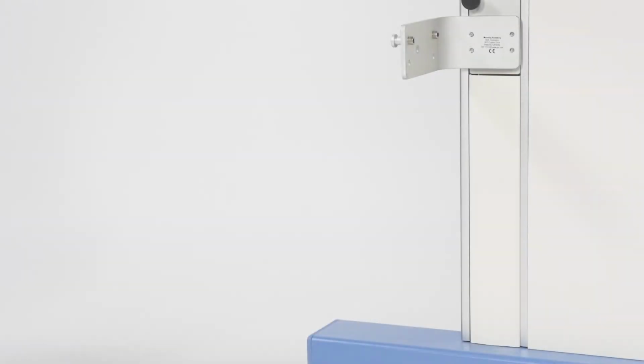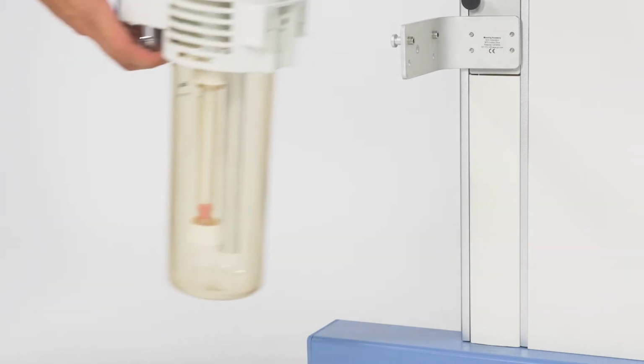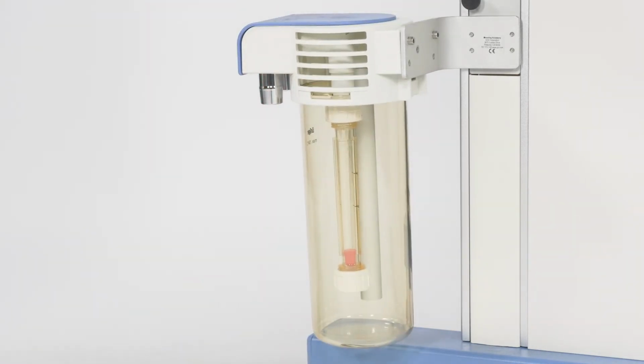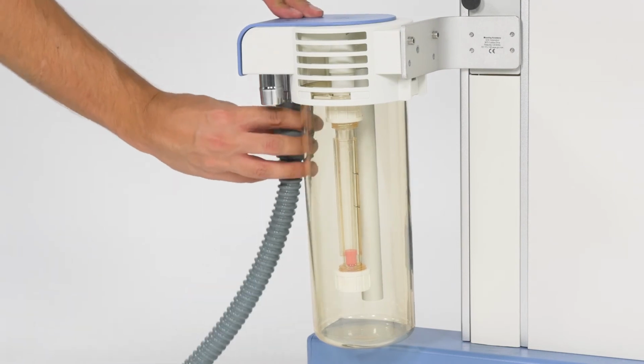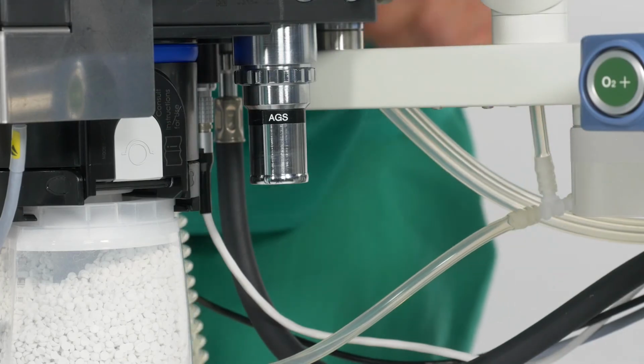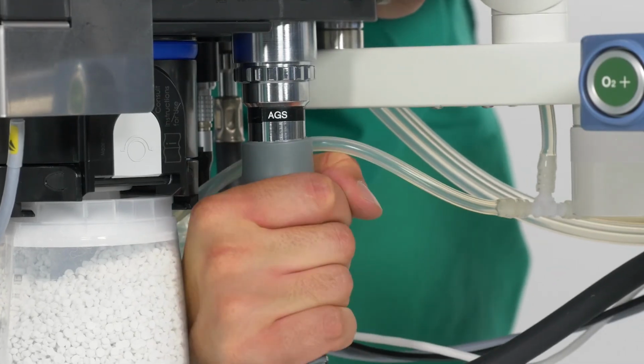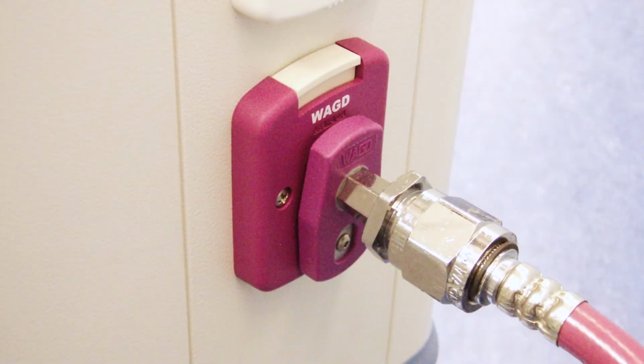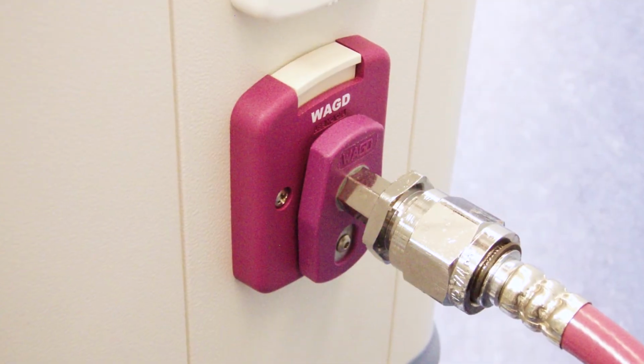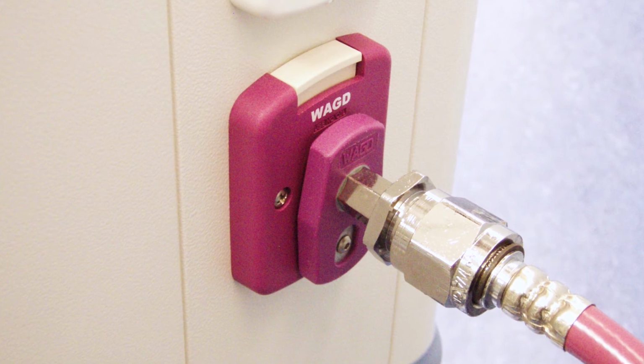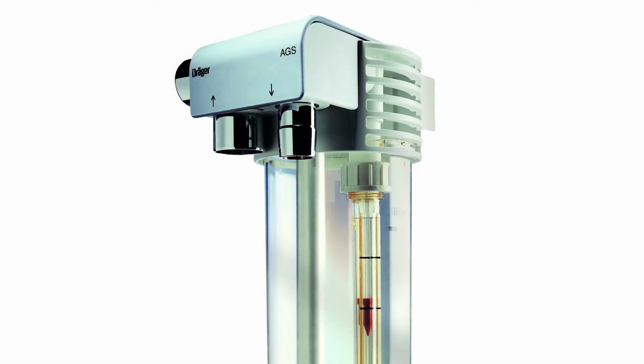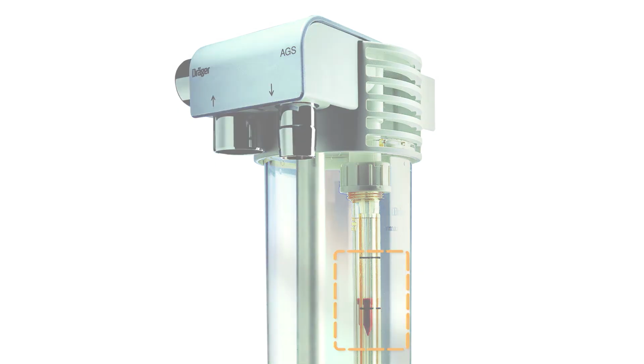For the assembly of the anaesthetic gas scavenging system, hook the receiving system into place on the rear side of the Fabius GS Premium. Then place the transfer hose between the receiving unit and the COSY. Finally, connect the scavenging hose from the receiving system to the central disposal system. To check correct operation of the waste gas disposal system, the float indicator in the flow tube should stay between the upper and lower marks.